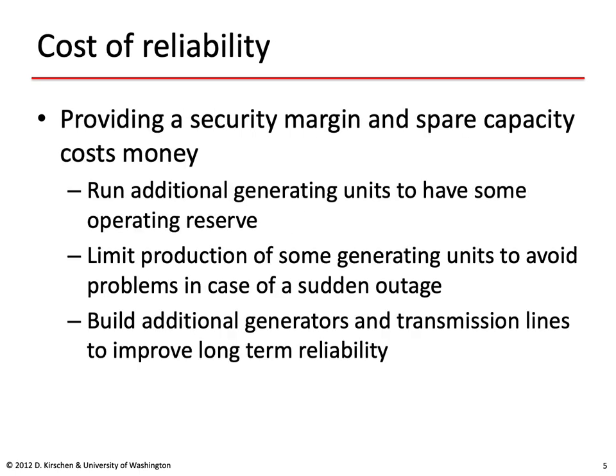Reliability has a cost in terms of providing a security margin and some spare capacity. In particular, we have to run additional generating units to have operating reserves. We have to limit production of some cheap units to avoid problems in case of a sudden outage in the transmission network, or we have to build additional generators and transmission lines to improve long-term planning reliability.